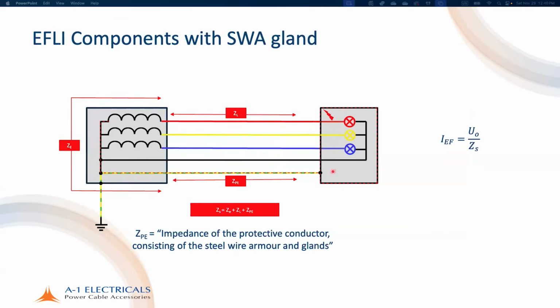There are none of these other issues. So the best thing to do is use an armored cable gland. See, oftentimes people are still scared, then they use a 5-core cable. But remember, the armor still has to be earthed either way. So an armor is perfectly fine to use as a PE conductor if the cable gland is correctly used.